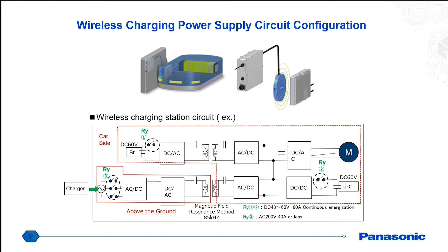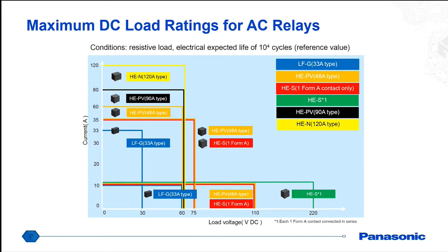One thing I did want to point out is a lot of the relays that we have for the mechanical side are AC relays. However, although they do not have the DC ratings on the actual data sheet, we do have a lot of reference test data we can provide showing the DC ratings. So for example, our HES relay can handle 35 amps at 75 volts DC, or it can handle 10 amps at 110 volts DC, even though it's rated for 277 volts AC. And that's just one example.